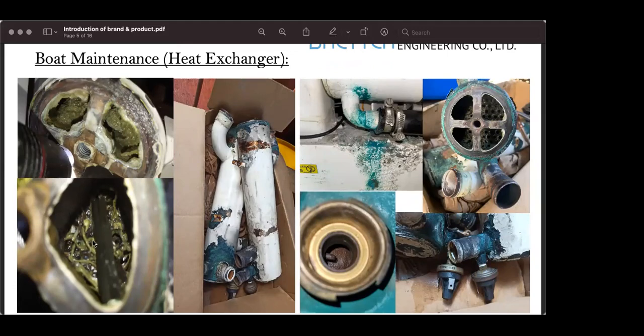And algae inside here. On the middle one, we can see it with a leaking heat exchanger. Leaking and corrosion, I guess. When the heat exchanger leaks, I can tell because inside is building too much pressure. When the water can't pass through, they have to find somewhere to expand, outward, because inside is blocked. So basically it's the pressure.